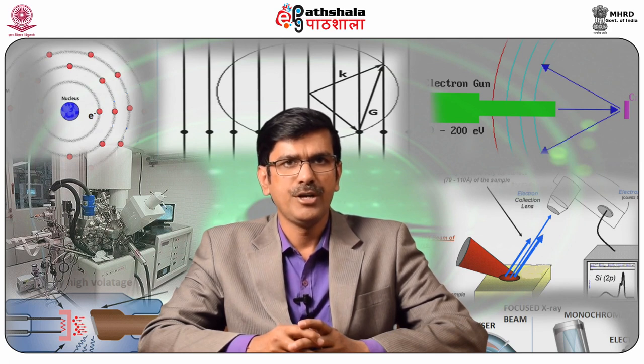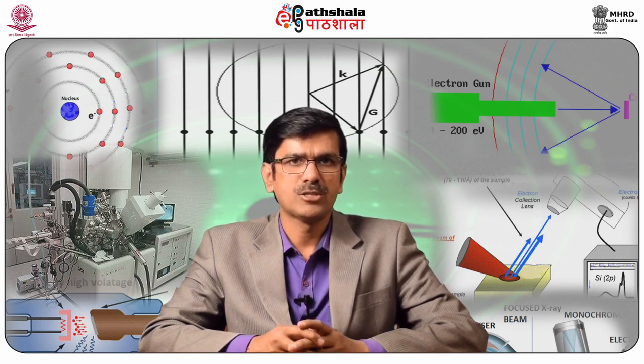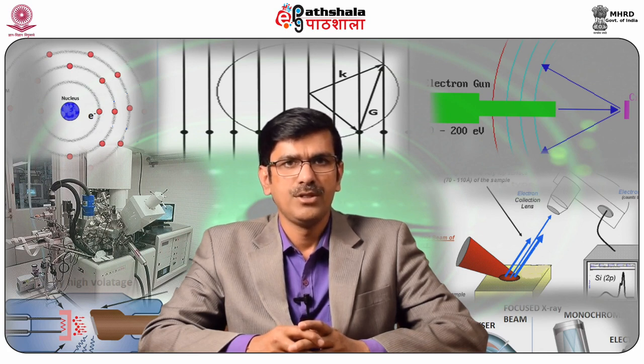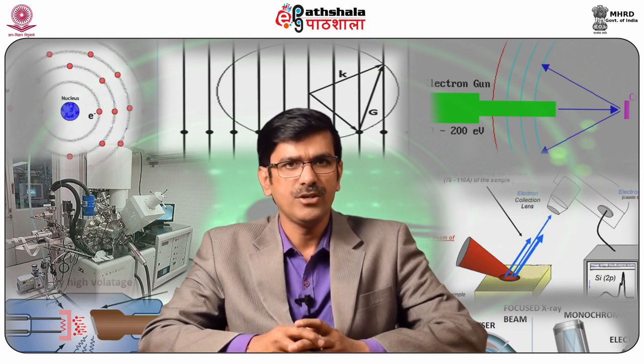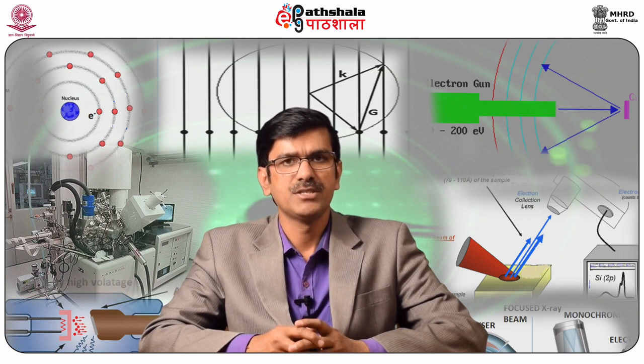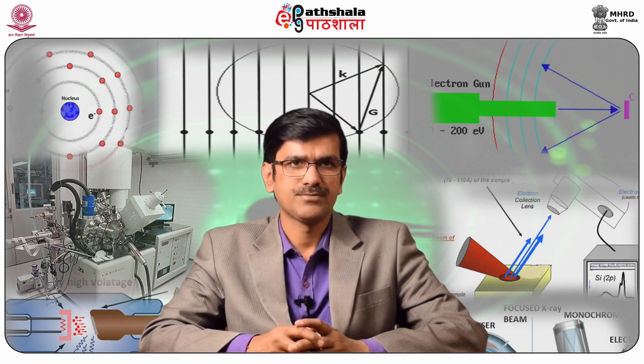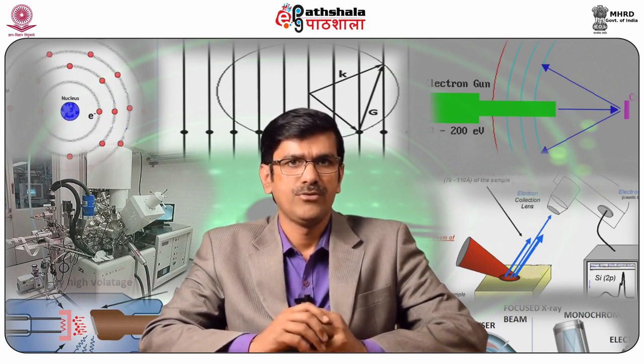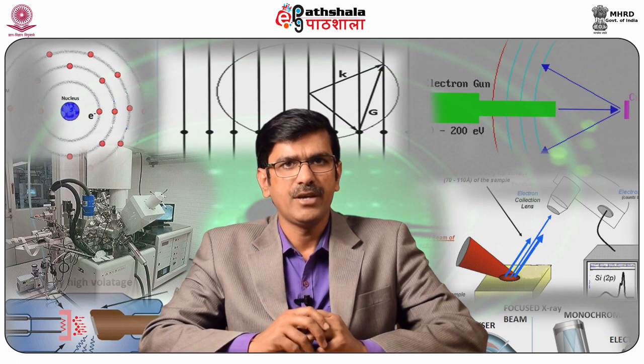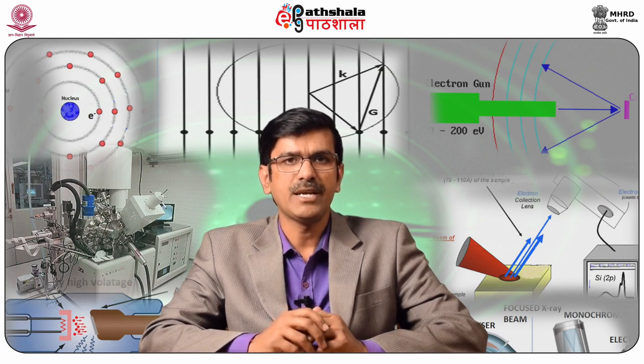Point 4: it is possible to focus X-rays into a small spot using the monochromator, meaning that small area XPS can be conducted with high sensitivity. Point 5: use of a focusing monochromator means that only the area of the specimen being analyzed is exposed to X-rays. Thus, a number of samples may be loaded into the spectrometer without the risk of X-rays damaging samples while they await analysis. Similarly, multipoint analysis can be performed on the same delicate samples.